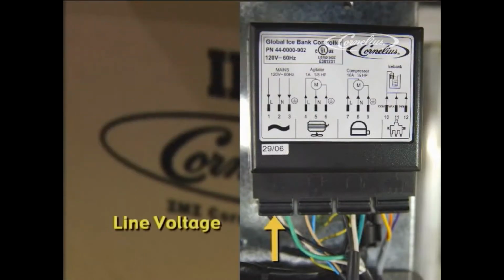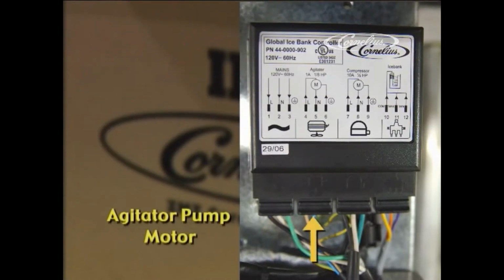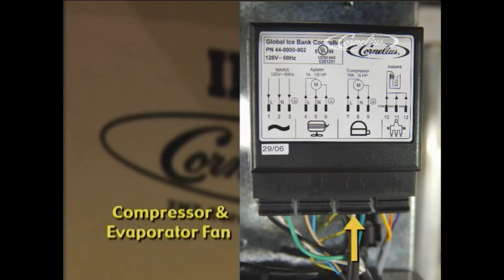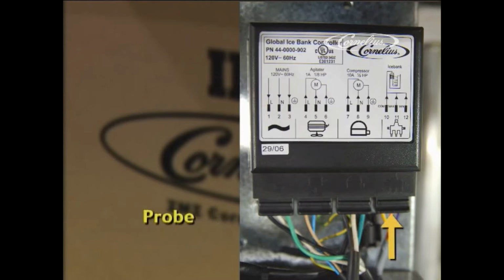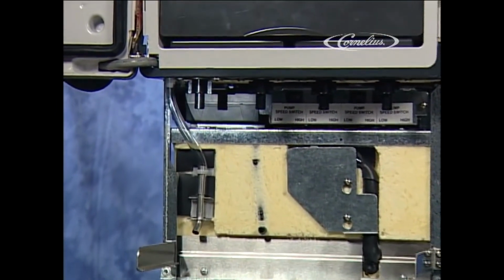The IBC works off of line voltage that comes into the control here. The agitator pump motor is plugged in at this position. This is pass-through voltage only, as this motor runs any time the unit is plugged in. This is the outlet that leads to the compressor and evaporator fan, and this is the probe. All the connectors are keyed so there can be no mixing them. The ice bank control is located here.